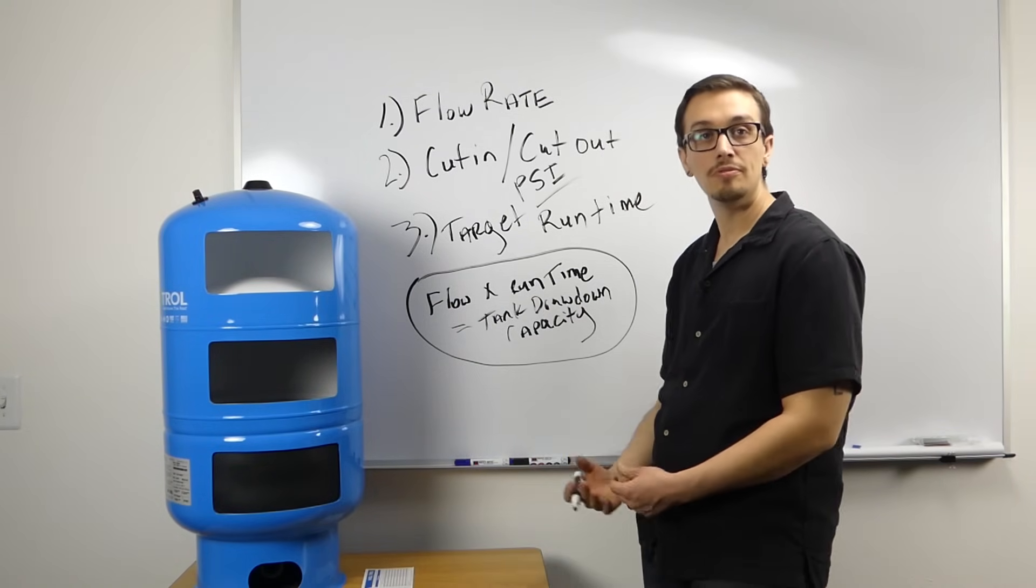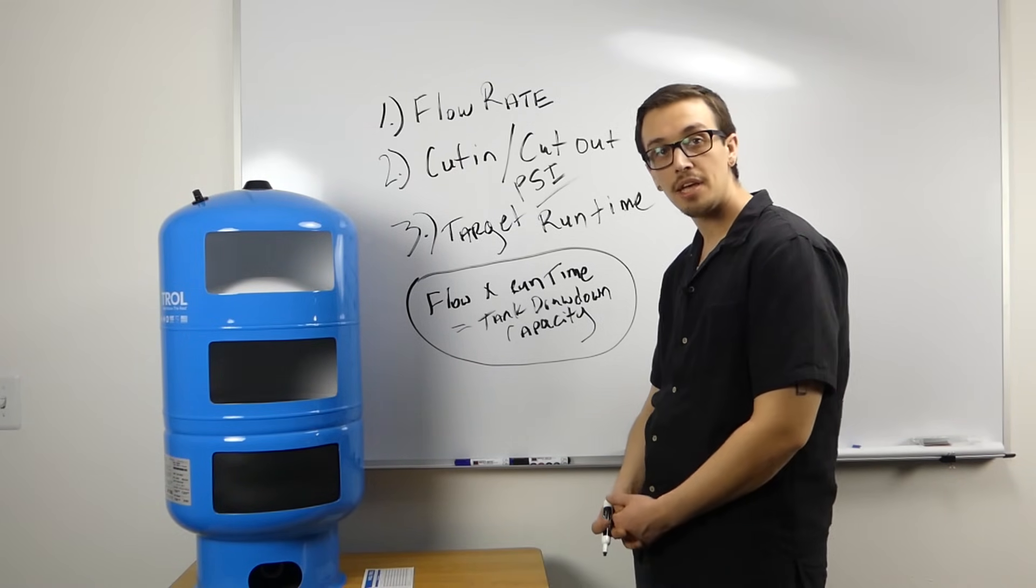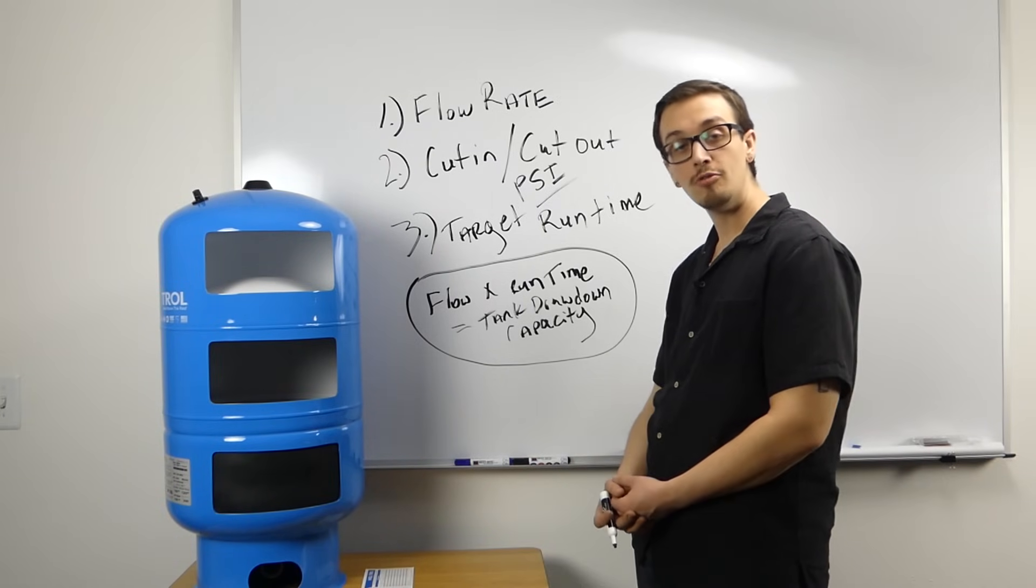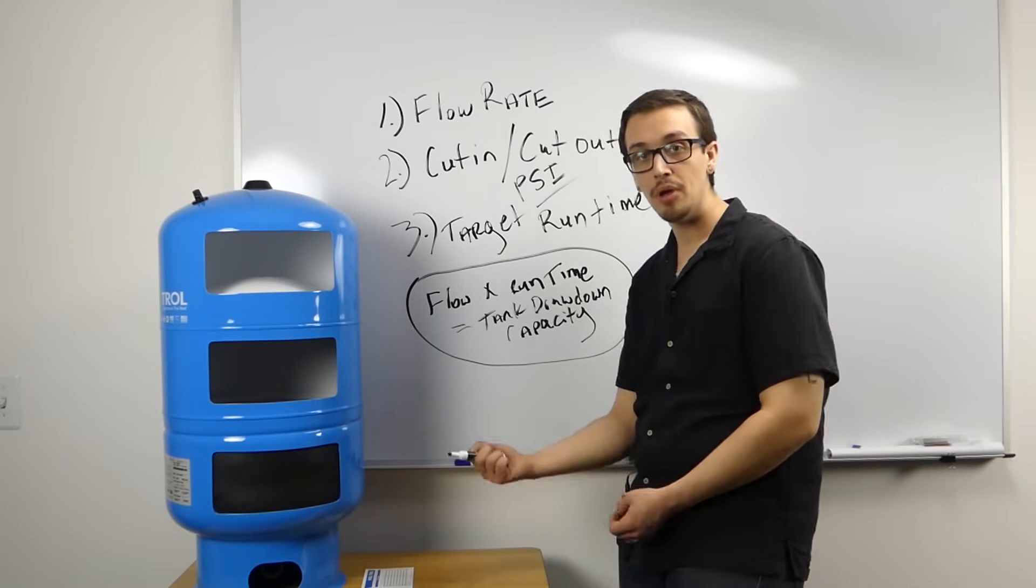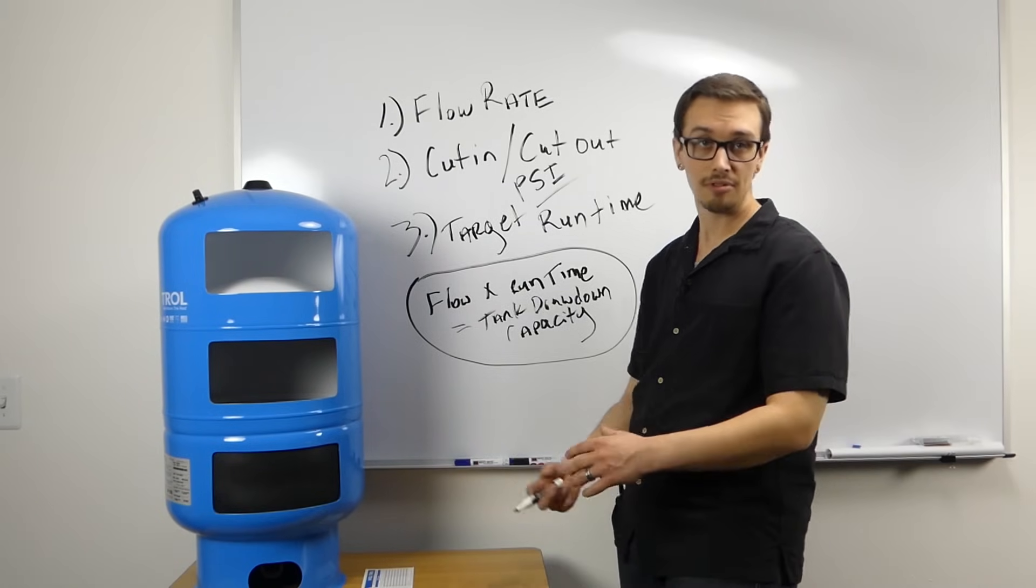Pumps with flow rates or capacities up to 10 gallons per minute should have a tank with a minimum of one gallon drawdown capacity for each gallon per minute of the pump. For example, a 10 gallon per minute pump would want to have roughly a 10 gallon drawdown capacity.